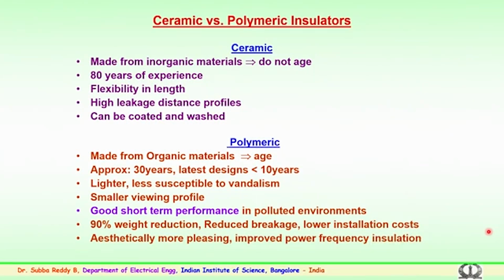So, we have seen the ceramic or porcelain performance and the polymer insulators. As mentioned, ceramic insulators are made from inorganic materials. These do not age, and they have more than 80 to 100 years of experience. There is flexibility in length, particularly with ceramic insulators: you can have a number of discs and increase the length. High leakage distance profiles could be manufactured without difficulty, and these can be coated and washed at regular intervals of time.